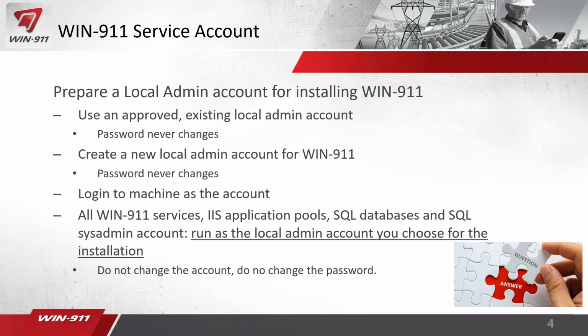And this is the most important part to understand, is why we need this local admin account and why the password should never change. All Win911 services, the IIS application pools, the SQL databases, and the SQL sysadmin account are going to run as the local admin account that you choose for the installation.